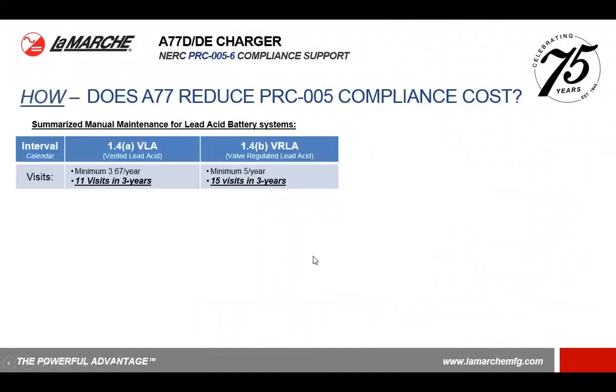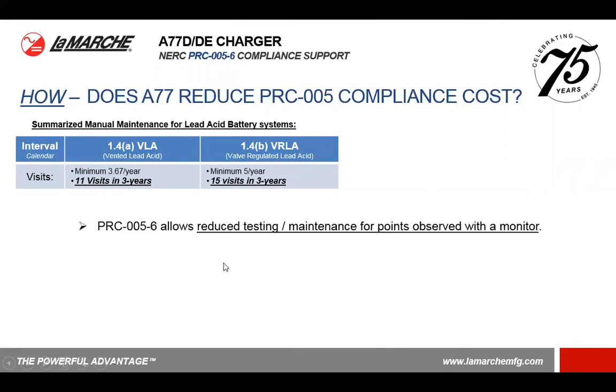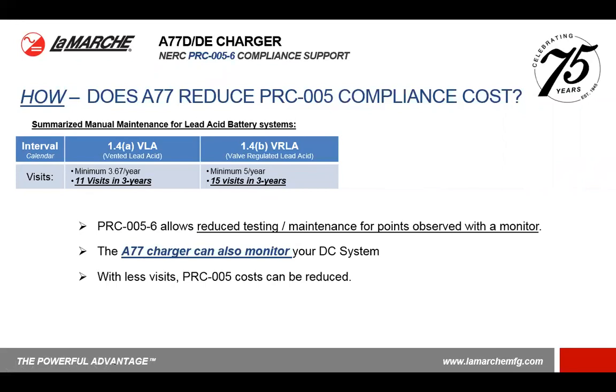So how does the A77 actually reduce your compliance cost to PRC-5? Well, let's look at the visits. For vented lead acid, ultimately you're doing roughly 11 visits over 3 years. In VRLA, you're doing 15 visits over 3 years. PRC-5-6 allows for reduced testing and maintenance for points observed with a monitor. The A77 can also monitor your DC system. And with fewer visits, your PRC-5 costs can be reduced.